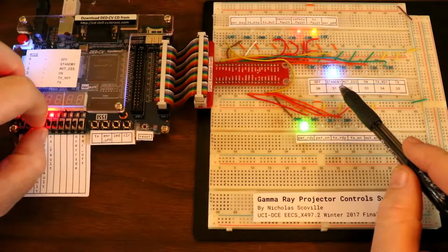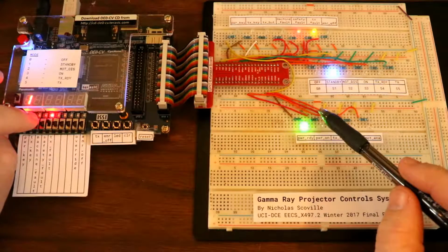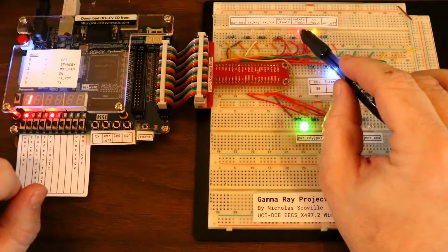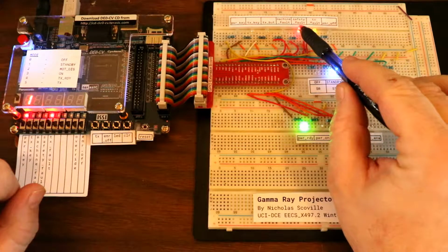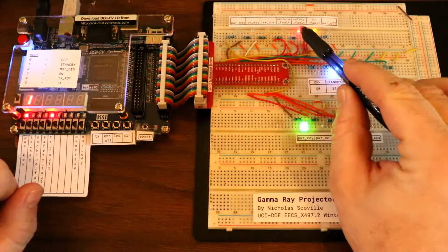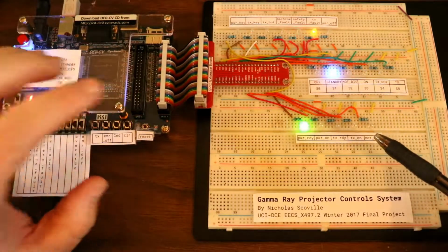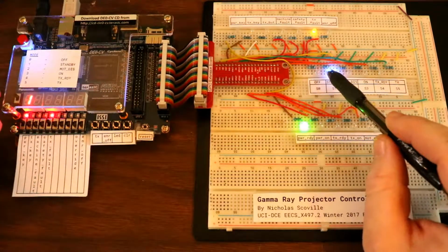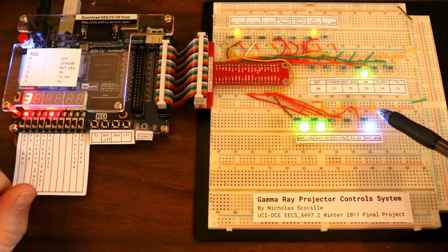So now if I remove the safety fault, it's removed there, but it's latched there because these two faults latch, meaning that even if the fault is momentary, you have to acknowledge the fault to make it go away. So now if I push clear, we should be able to turn the key off and turn it back on and get back to the on state.